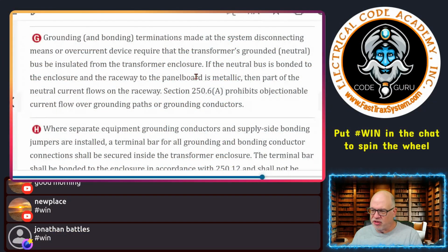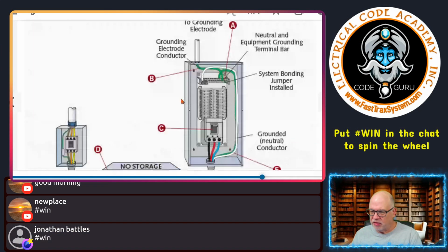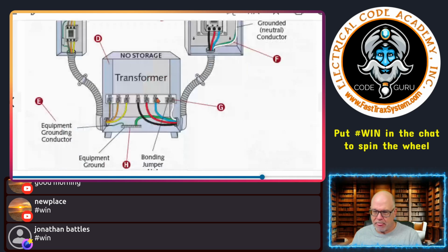All right, now H, the last one, and that is right here. These are your terminations for your equipment grounds. This is where your termination for your supply side bonding jumper goes, the one going up with this raceway that again doesn't qualify because it is flexible. So it requires a wire type supply side bonding jumper to go with it, okay? But also this bus could be where the XO puts the supply side bonding jumper over here.